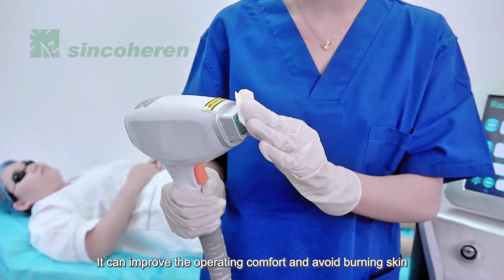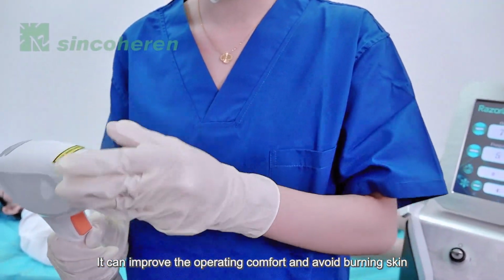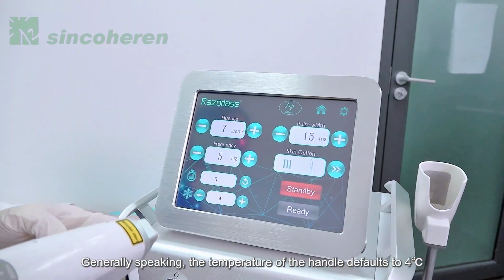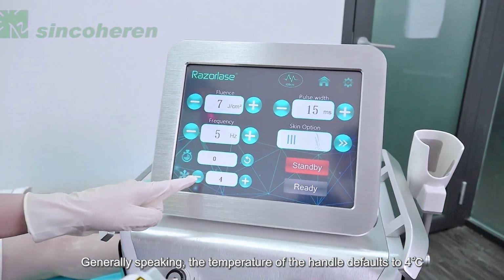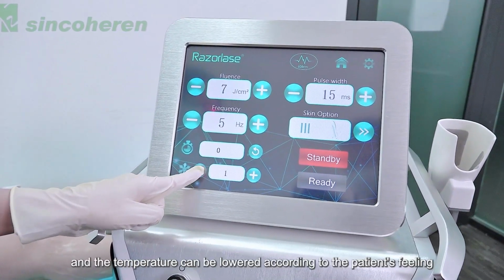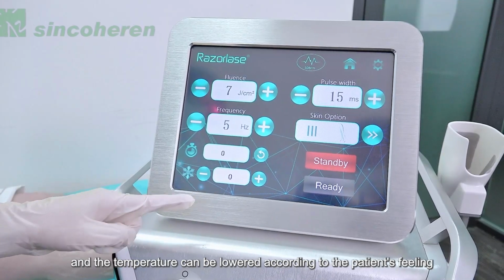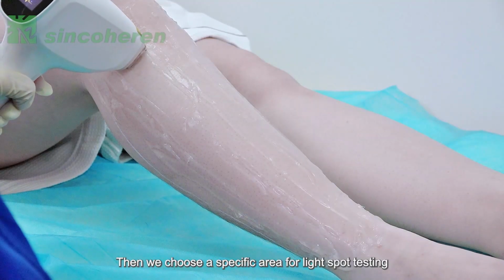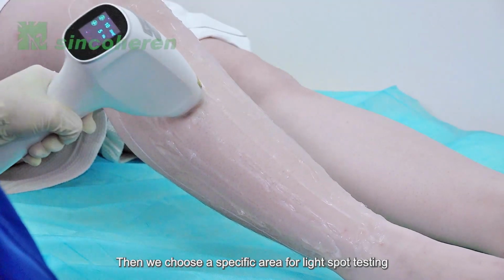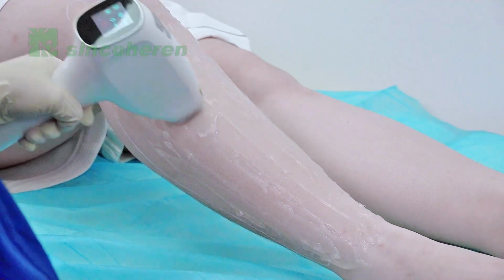It can improve the operating comfort, and avoid burning skin. Generally speaking, the temperature of the handle defaults to 4 degrees Celsius. And the temperature can be lowered according to the patient's feeling. Then we choose a specific area for light spot testing.